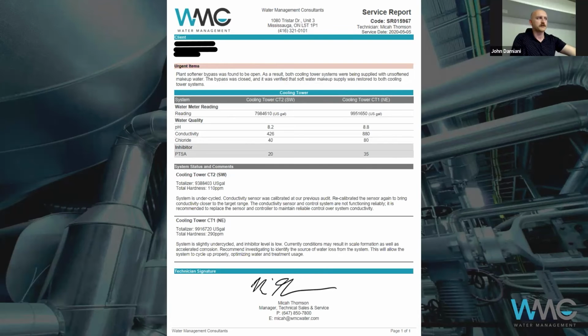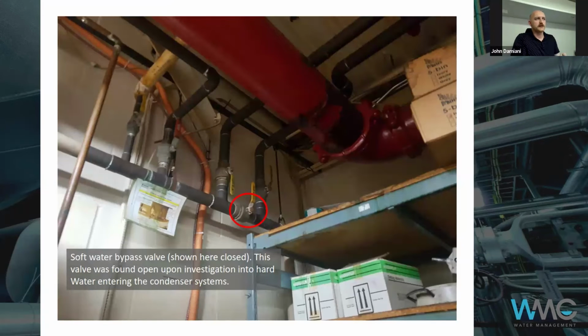Some urgent items in this case. When we do an audit, we really like to communicate with the customer and make them aware of exactly what's going on. In this case, we had a cooling tower that was fed partially, or supposed to be fed partially, soft water - that's a strategy you can use to increase your cycles. But here the bypass valve was open and they weren't feeding any soft water to the system, and they didn't adjust their water treatment program.